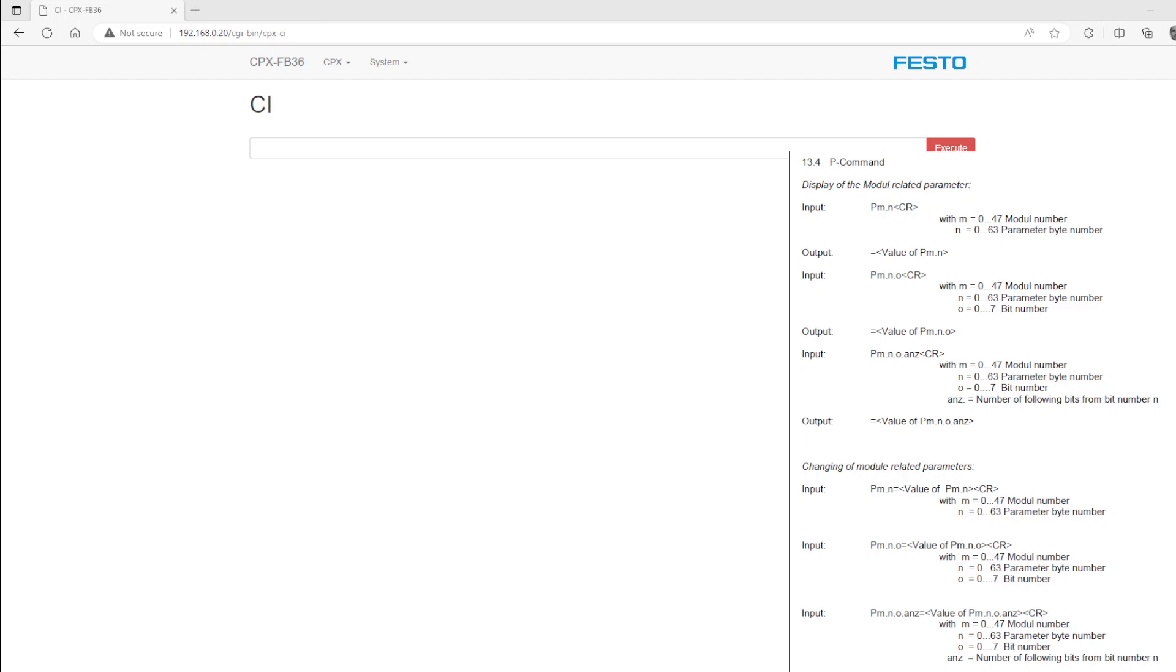So all I'm going to do is change the IP address from .0.20 to .0.21. First thing I'll do is display the current IP address, subnet, and gateway. You can see the syntax for that is PM for module, which will be zero. The first position, that's CPXFB36, was in the zero-th position, or the first place.